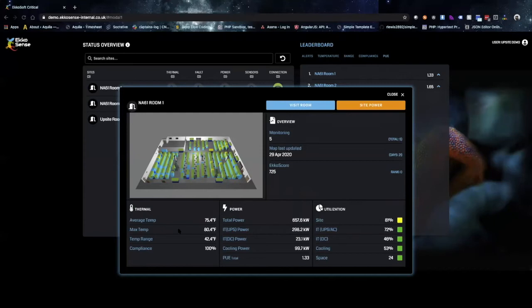Then you'll go to the thermal pane. So you'll see the average temperature of the intakes of all the racks in the room, the max temperature of those intakes, the temperature range, and the compliance once again. So then we can move into the power pane. You'll see total power, which is site-wide power. Then the next two are specific room level powers, so UPS power as well as DC power. Then you can see the cooling power that this room is currently using, as well as the PUE once again.